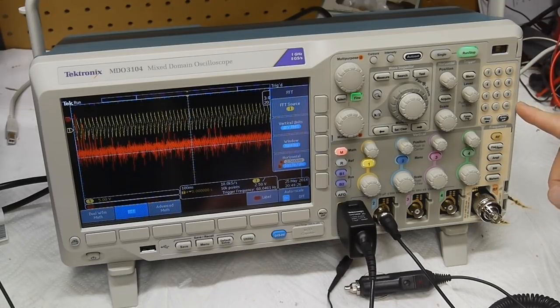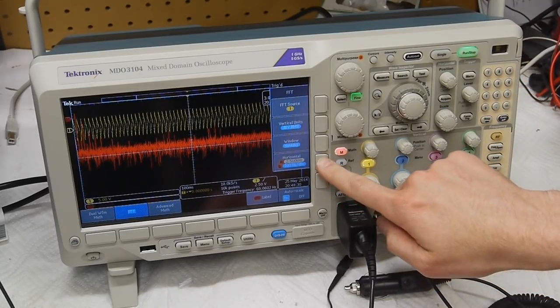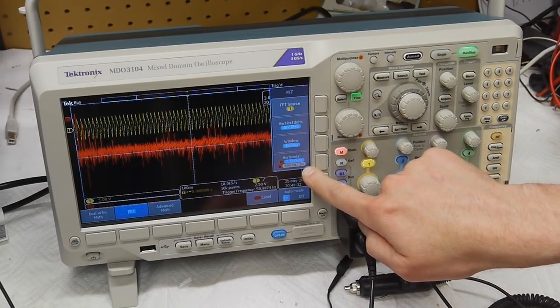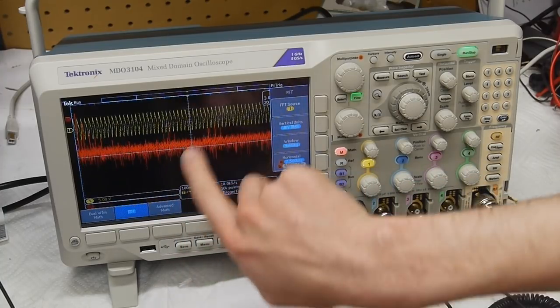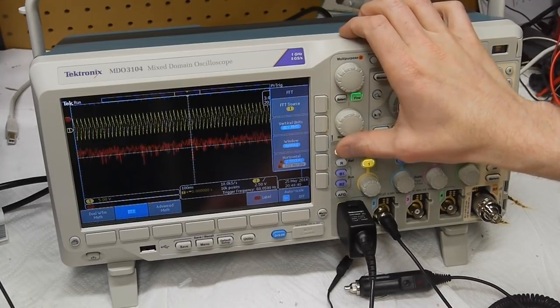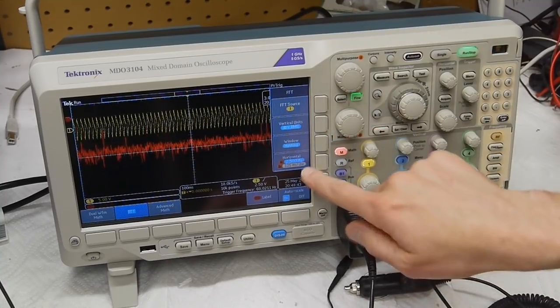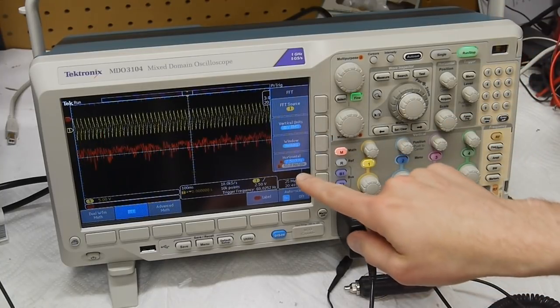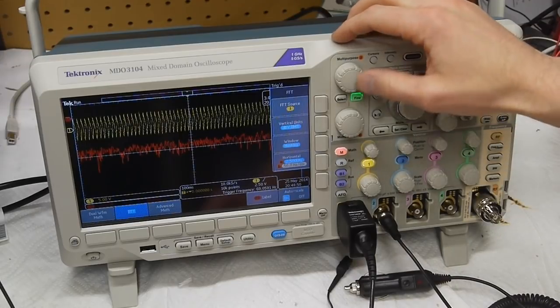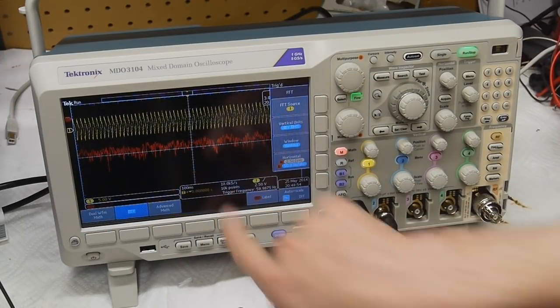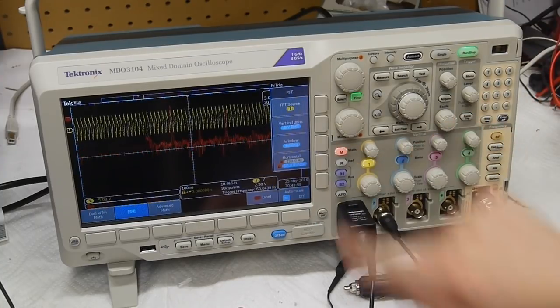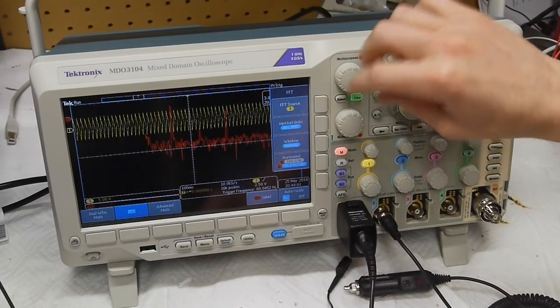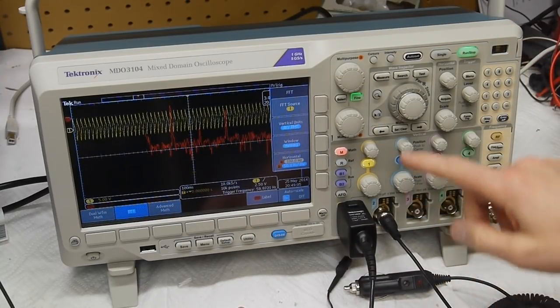One thing I like about the Tektronix that I haven't seen on many other scopes is the numeric entry. So down here we can change the center point and spatial resolution or frequency resolution of the FFT. And you could use the knob to do this, but if you already know what you want, like I already know that I want maybe about 50 hertz for the frequency per division. And if we want to change the center point, we could set the center point to be something like 100 hertz. And then we've already dialed this thing in without dealing with the wheels here. I thought that was a nice feature that doesn't show up too often.